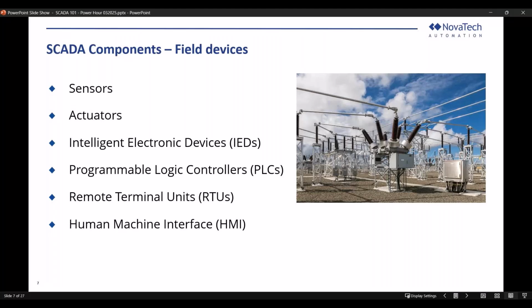Human machine interface, this is quite important because you have so much data coming into your system, and no human, no technicians, no engineers can analyze all that data quickly. So you want to present that data in more of a user-friendly format, for example a one-line diagram, an alarm annunciator. You want the ability for a human to interact with the system, so a web UI is a form of HMI, how to send controls, how to set a parameter. Those are all HMIs within the system, the ability for a human to interact with your SCADA system.